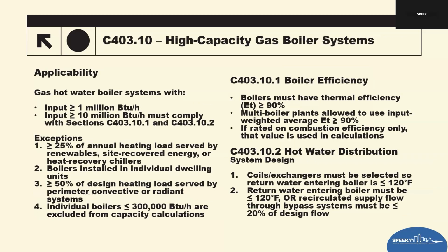So, large commercial boiler systems, especially those over 1 million BTUs per hour. These systems are commonly found in large schools, offices, hospitals, government buildings. The code now introduces requirements to increase boiler efficiency and improve hot water distribution design. So, applicability and intent. These requirements apply when total boiler plant capacity falls between 1 to 10 million BTUs per hour.